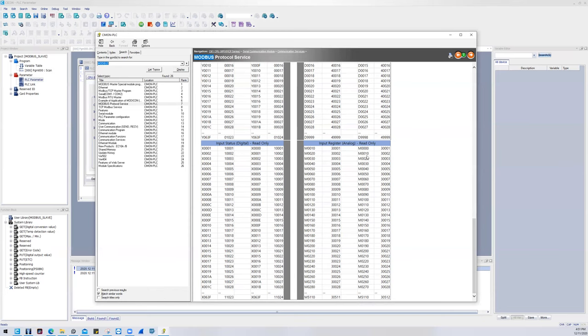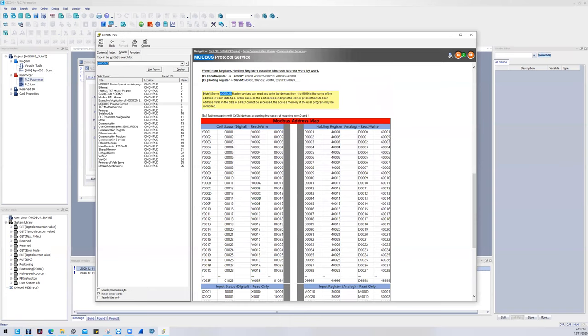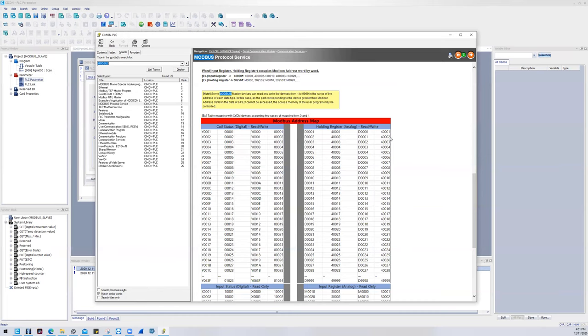Now there's one more tip I want to give you before I leave you that is targeting the bitwise of the words. So if I wanted to target the third bit of a D register, I would append the register 40,002, for example, with a dot three. That means I would be targeting the third bit of D0001.